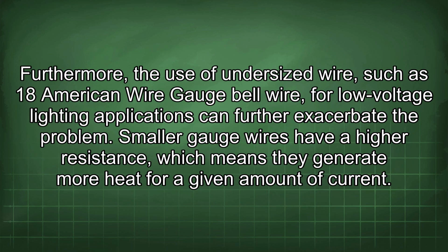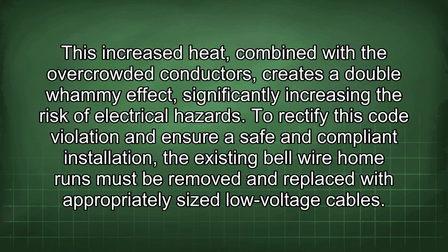Furthermore, the use of undersized wire, such as 18 American wire gauge bell wire, for low voltage lighting applications can further exacerbate the problem. Smaller gauge wires have a higher resistance, which means they generate more heat for a given amount of current. This increased heat, combined with the overcrowded conductors, creates a double whammy effect, significantly increasing the risk of electrical hazards. To rectify this code violation and ensure a safe and compliant installation, the existing bell wire home runs must be removed and replaced with appropriately sized low voltage cables.